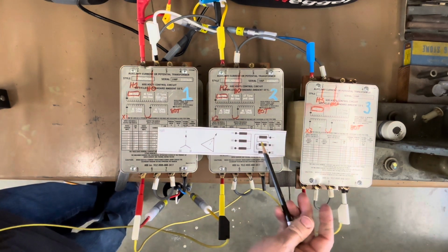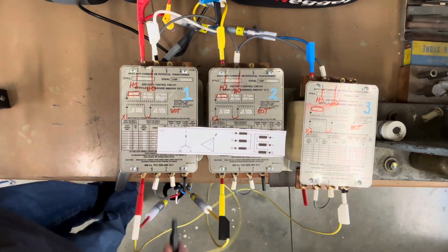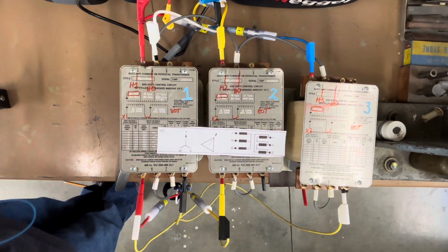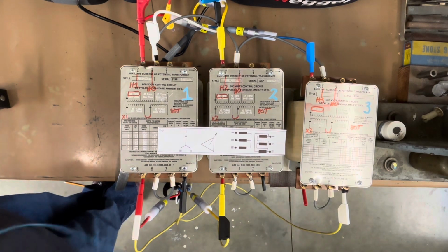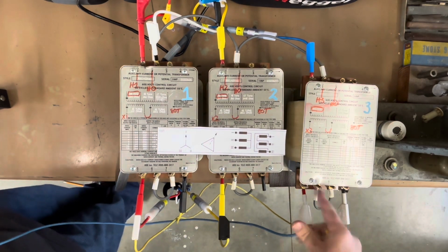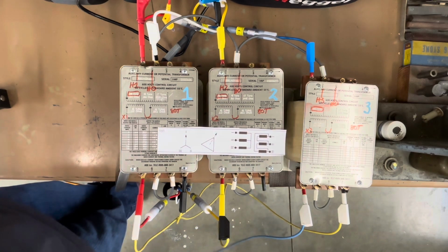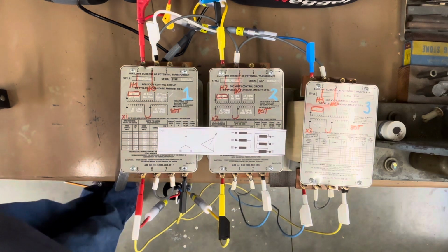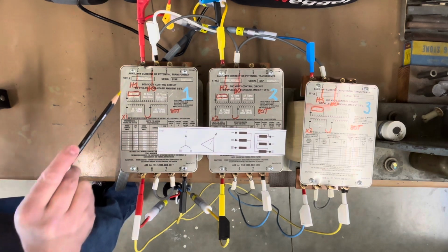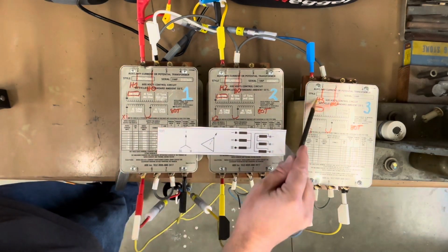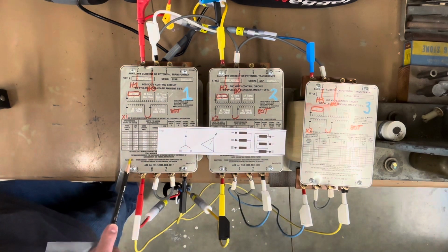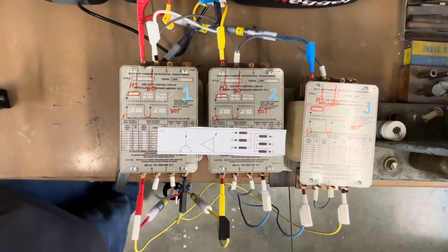to non-spot of 1. Last one's going from spot of 3 to non-spot of 2. You can pause it for a second, take a look at it if you want to. So, keeping with the nameplate that we showed earlier, this will now be H1, H2, H3, any one of these will be H0, and then we have X1, X2, and X3 of the delta.